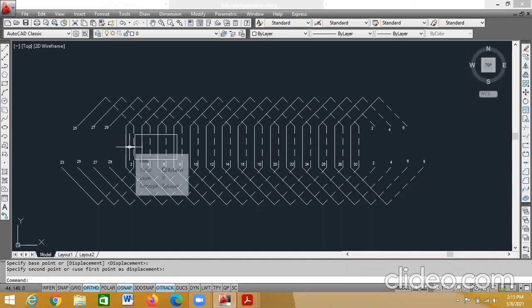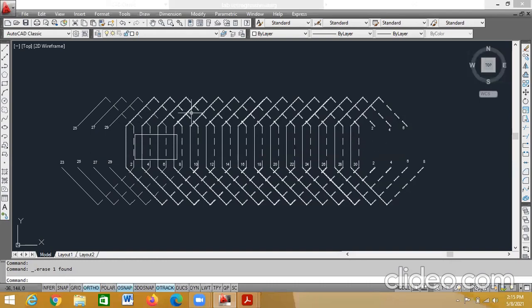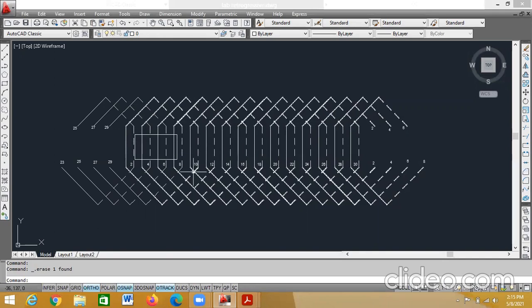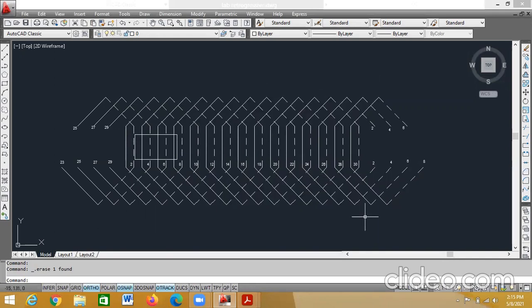So now delete this 0.15 tau line. Delete it. How many poles you want? 4 poles we require. What is the distance? Tau, tau, tau. So tau means how much? 7.5. So the clearance should be 7.5, 7.5, 7.5, 7.5. Within that, your pole should come.